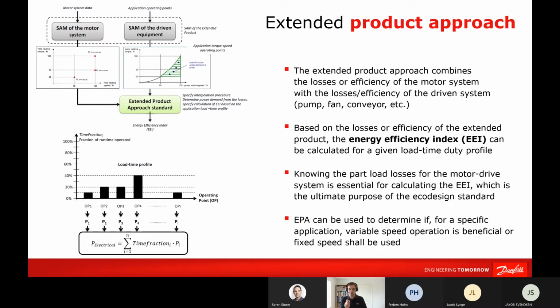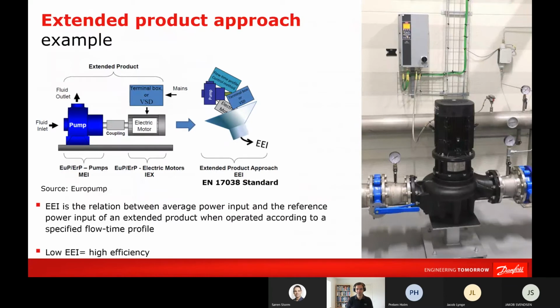Knowing these part load losses of the motor and of the variable speed drive, it's essential to calculate this energy efficiency index. And the extended product approach can also be used to determine if for a specific application it makes sense to use variable speed operation, or it makes more sense to still run at fixed speed. Now, to be more specific, I have an example here.